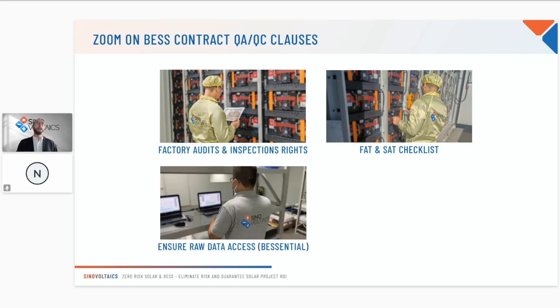Then, ensure raw data access. It's related to our BESS Essential service — during the FAT, with BESS Essential, we collect raw data from the BESS generated during the performance test. And we are seeing lately some roadblocks from manufacturers to provide this raw data. For me, that's a massive red flag, because there is absolutely no reason that should prevent the manufacturer from sharing raw data generated during the FAT, especially considering that you are buying a container worth hundreds of thousands of euros or US dollars. So you should have the right to access this raw data — make sure of it by including it in your contract.